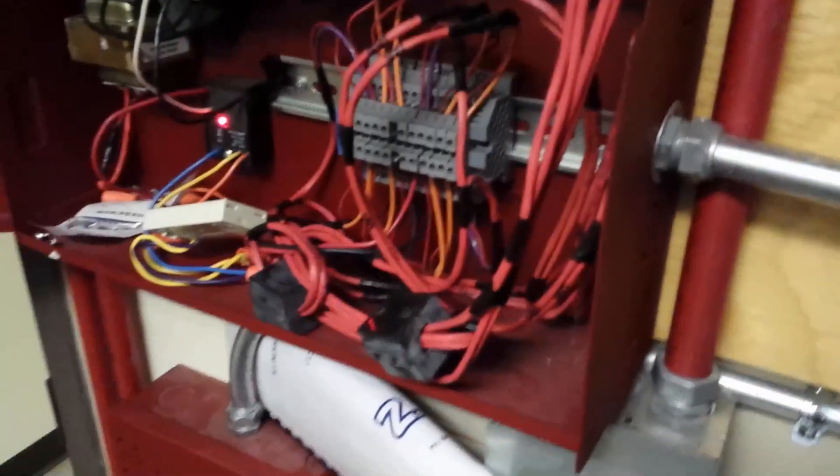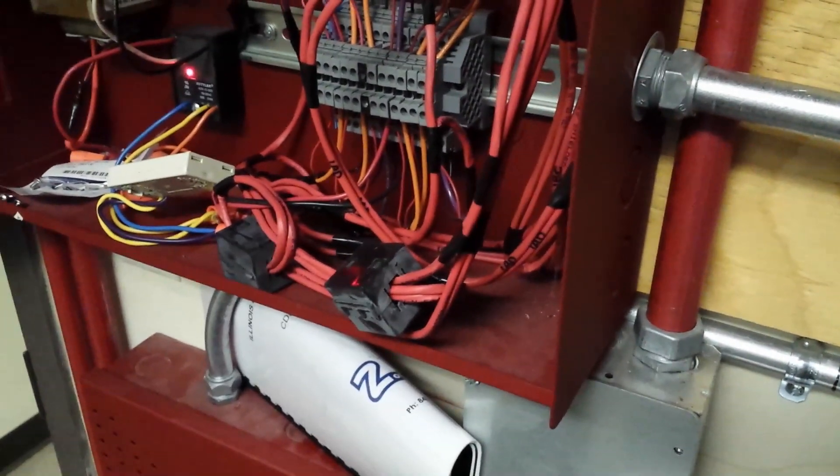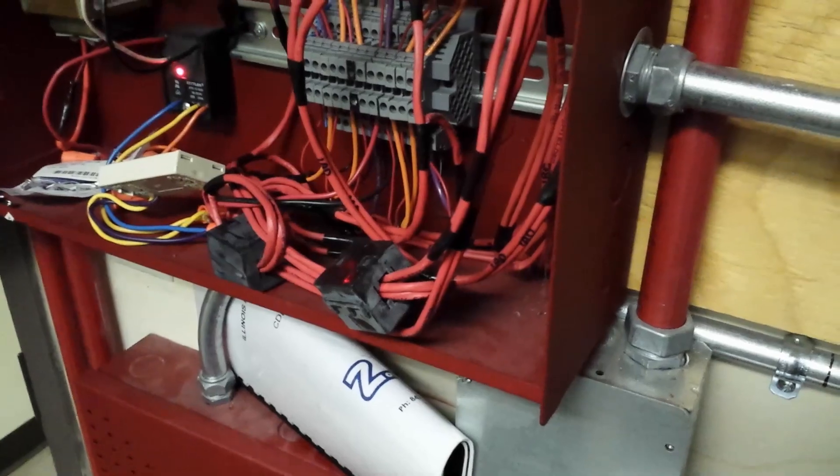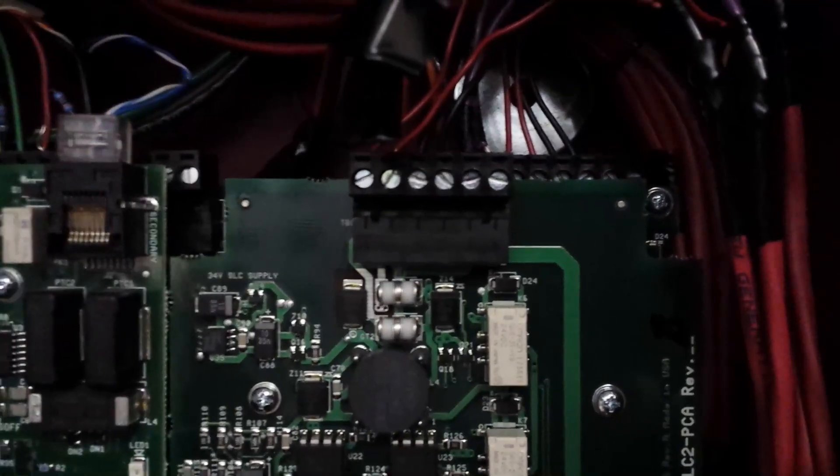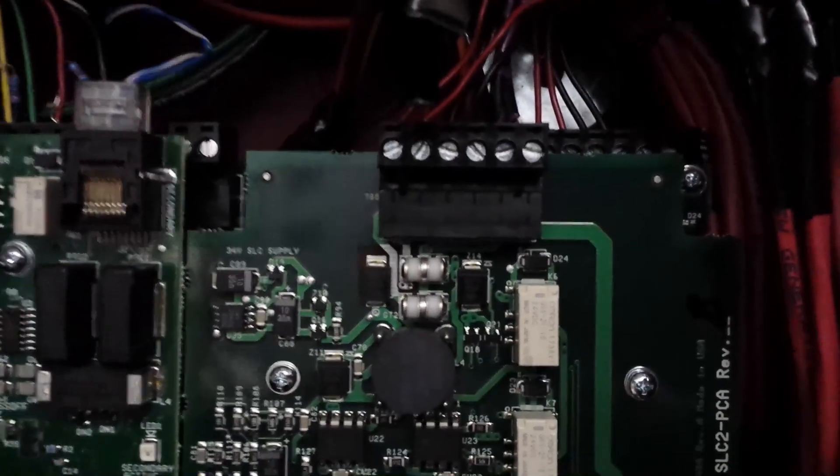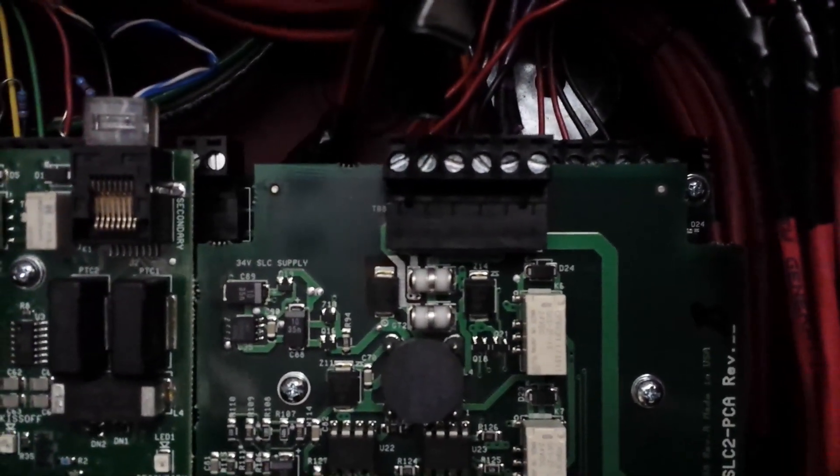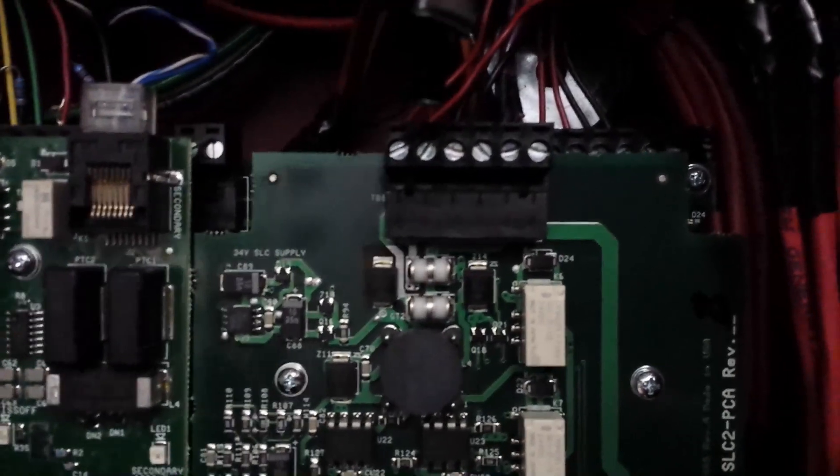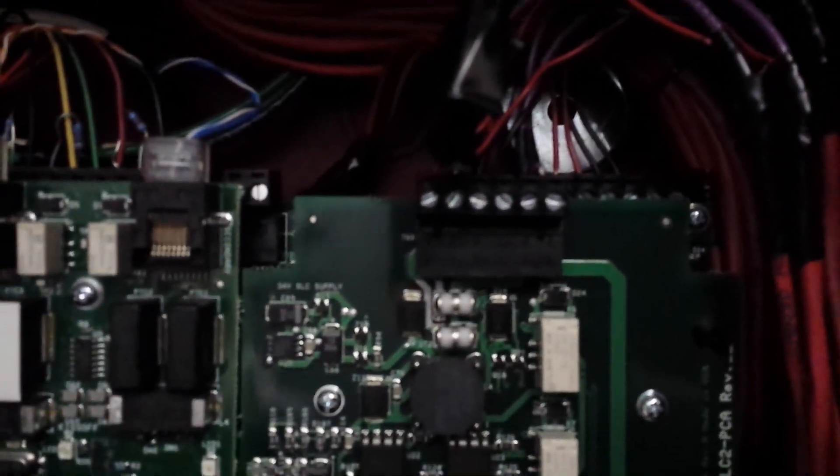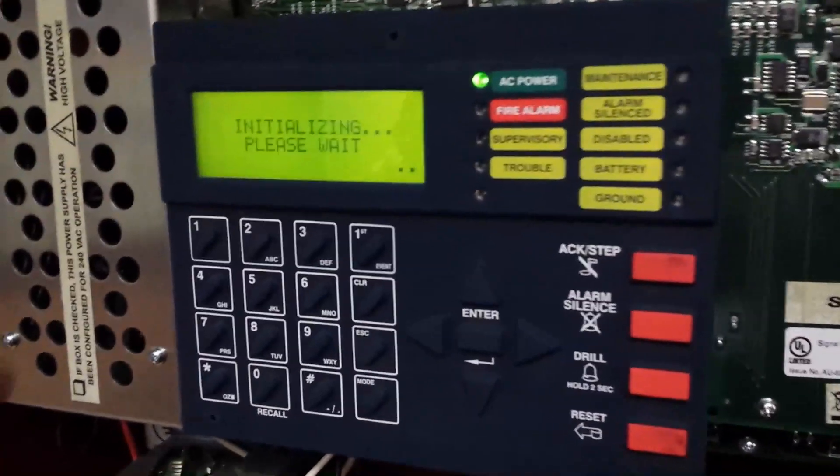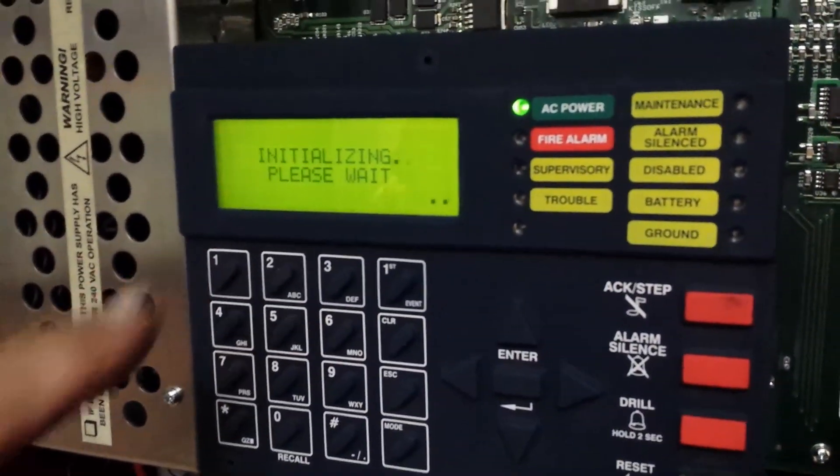When we were upstairs before, we left the pull station activated. The next step in the troubleshooting, I came down here and I lifted the SLC, because we were going to start looking at stuff, and I lifted the SLC and a bunch of troubles came in. I put the SLC back down and literally 10 seconds later, the alarm went off because we hadn't reset the pull station that did not activate previously. I just went up and reset the pull station now, and reset the panel a minute or two ago.